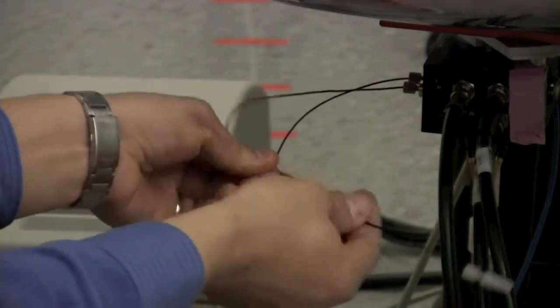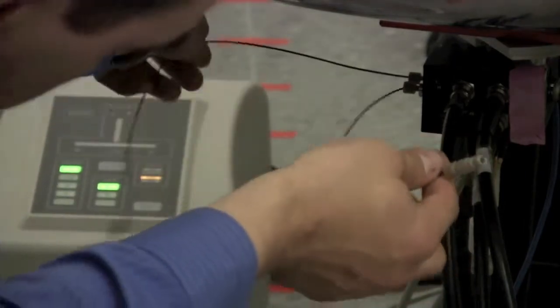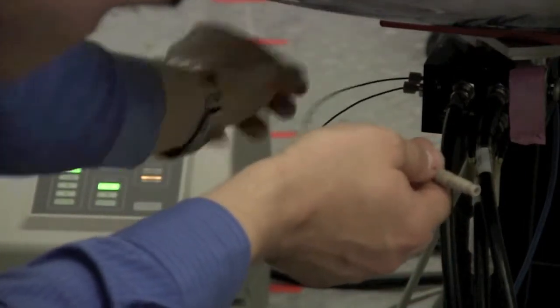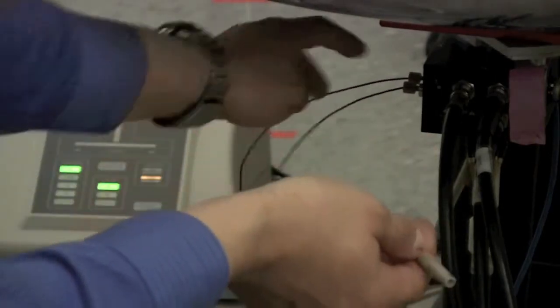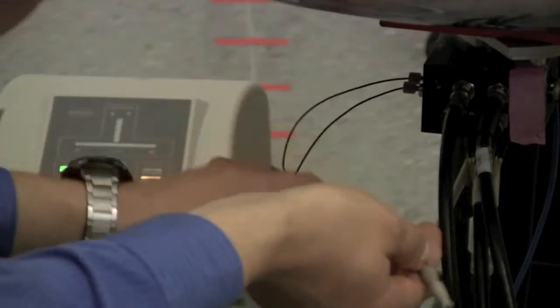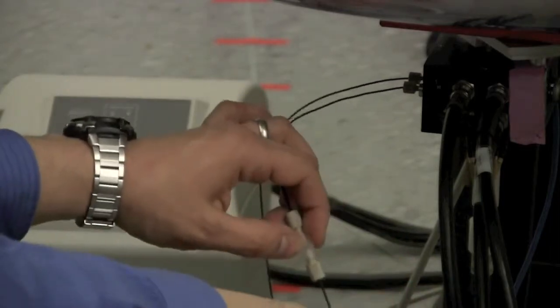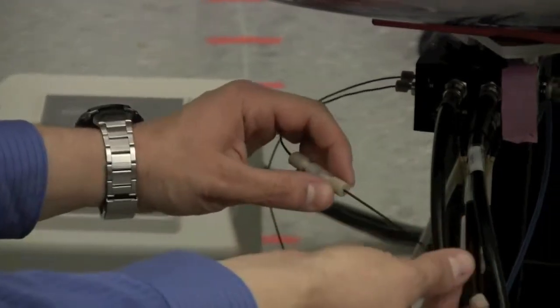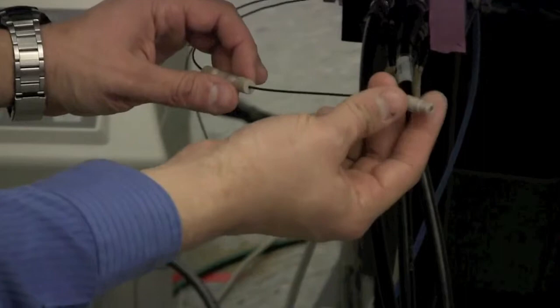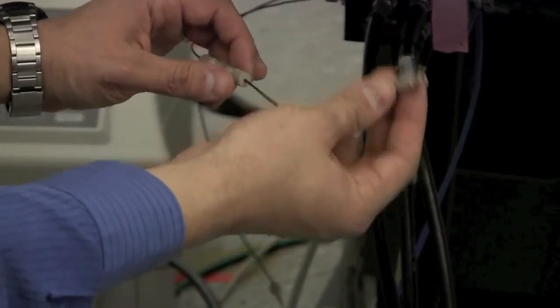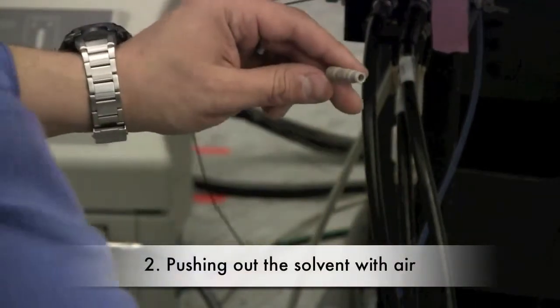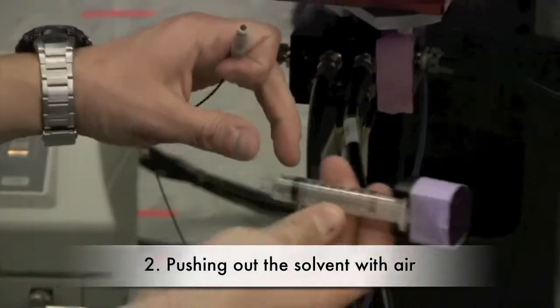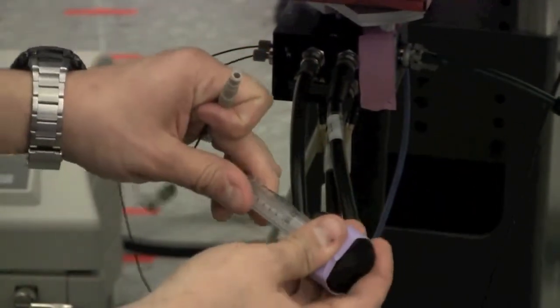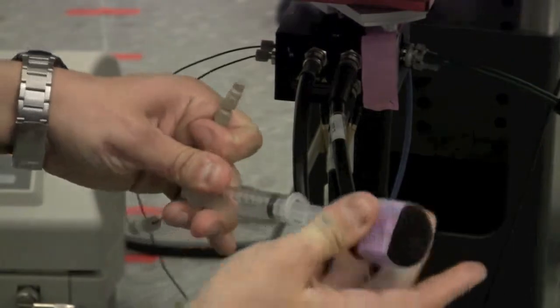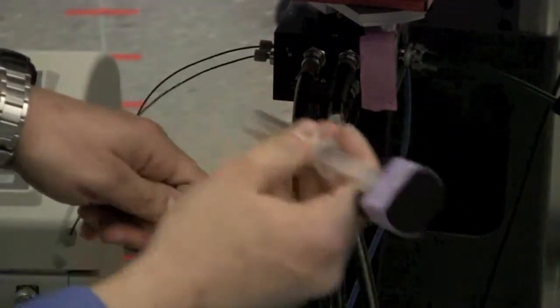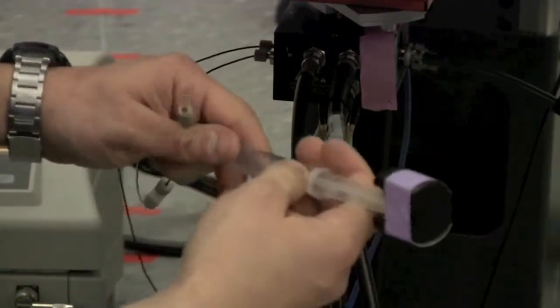Okay, so we have the outlet line and that's symmetrical on both sides, and then this long line that has an angled connection and a flat connection goes to the filter, and then the filter goes to this adapter, which finally goes to the luer lock connection, which is used for a syringe. So the first syringe we're going to put on there is this big one, this 10 milliliter syringe. This one we're just going to use to push out any solvent that's in there with air.